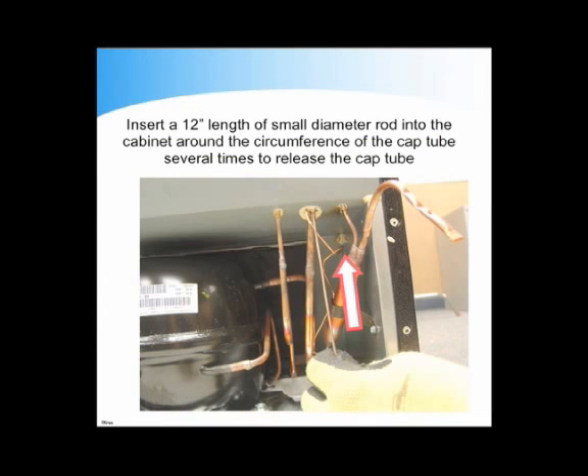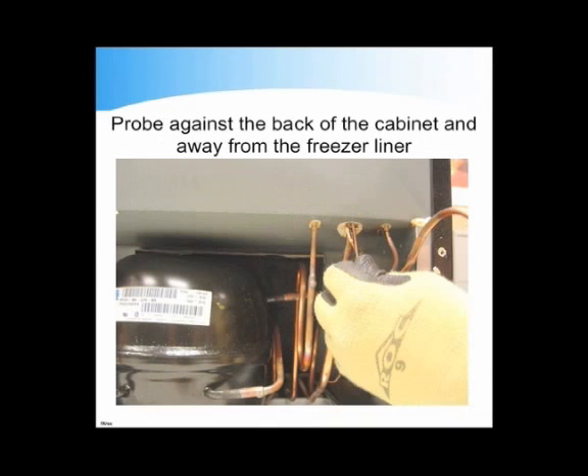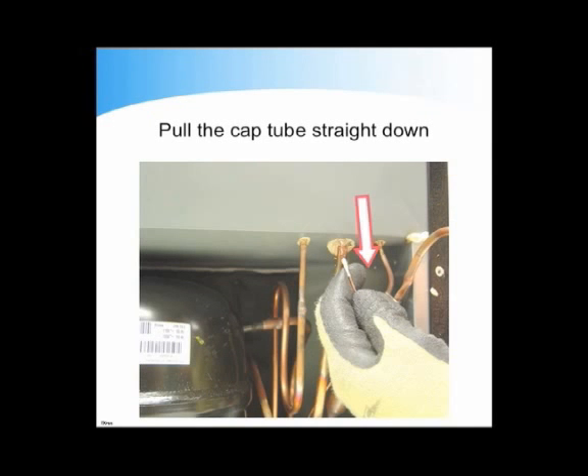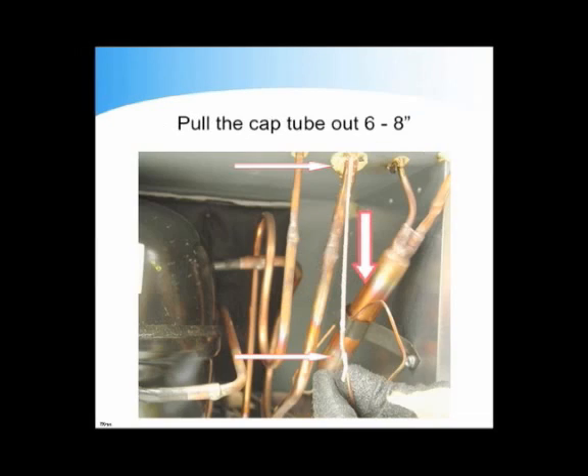Insert a 12-inch length of small diameter rod into the cabinet around the circumference of the cap tube several times to release the cap tube. Probe against the back of the cabinet and away from the freezer liner. Pull the cap tube straight down. Pull the cap tube out 6 to 8 inches.